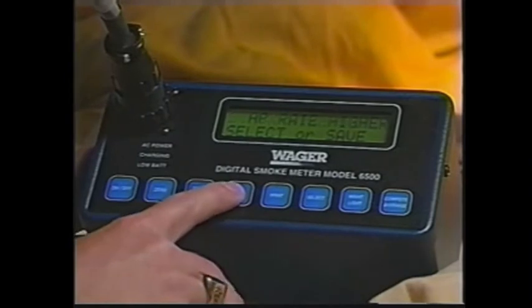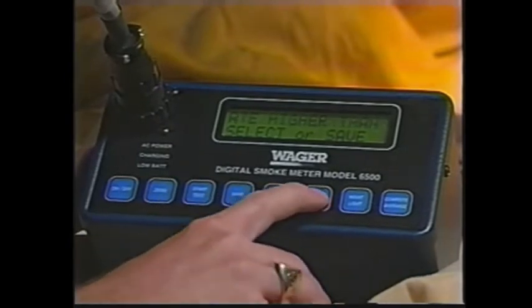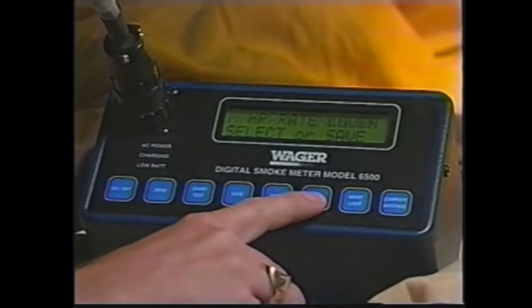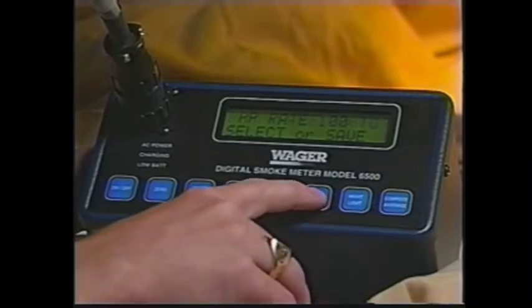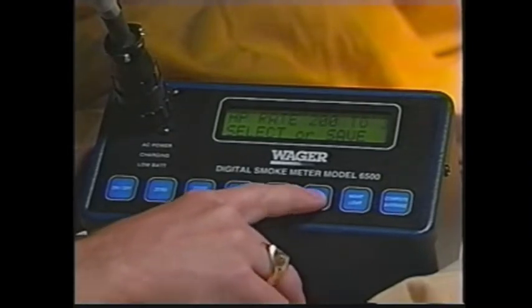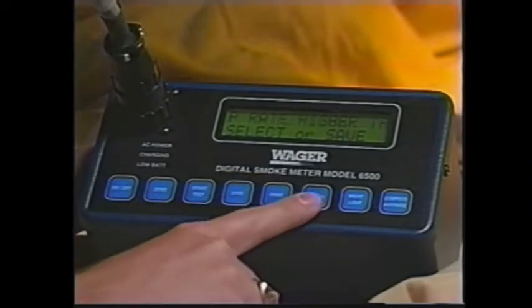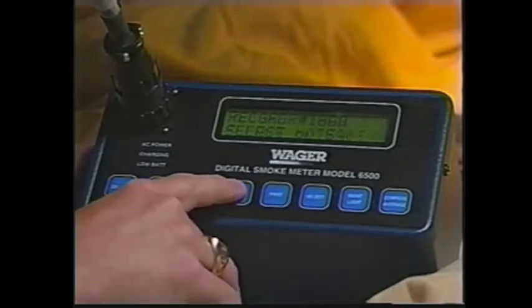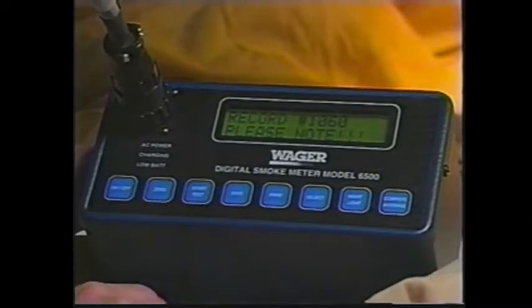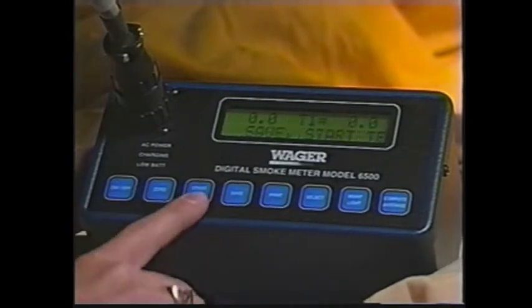The horsepower displayed is the default rating for the selected stack size. To change this setting, press select, then press save. You are now ready to perform the 3 preliminary tests required under SAE J1667. The display will give you the prompt Start Test.